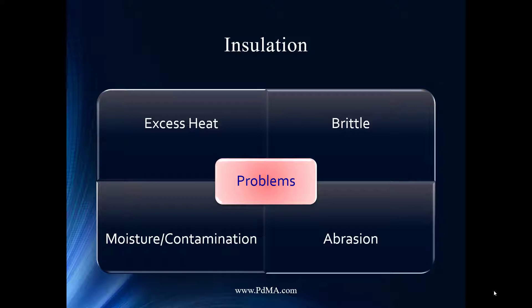Insulation is classified as Class A, B, F, and H — all controlled by temperature. What happens if you exceed that temperature? A well-known rule of thumb is that for every 10 degrees above the design temperature, you cut the insulation life in half. So if you have a Class F insulation with a winding temperature above 155°C, getting just 10 degrees above that could reduce insulation system life by 50 percent.